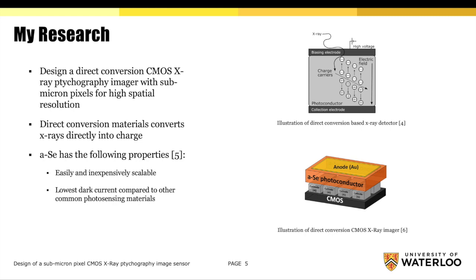Using an amorphous selenium film with an applied bias allows for high x-ray absorption and high spatial resolution, and this enables a significant reduction in pixel size and overcomes the challenge presented by scintillator-based x-ray detectors.